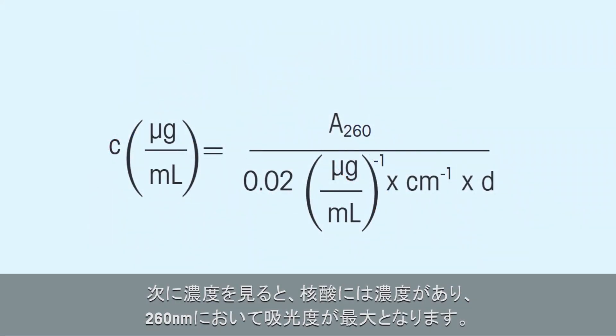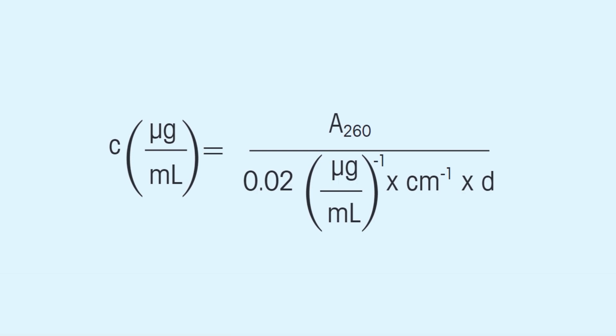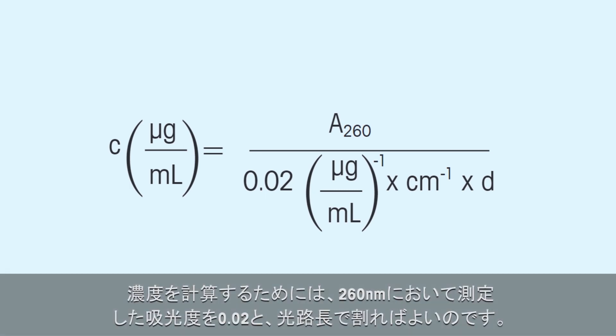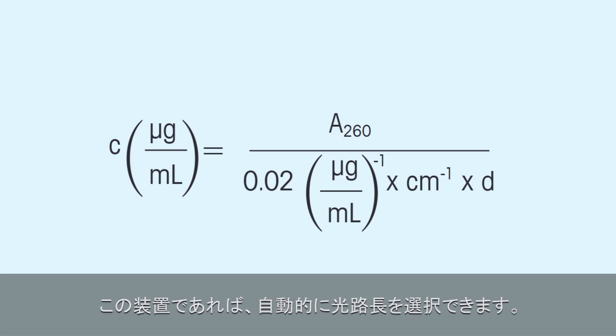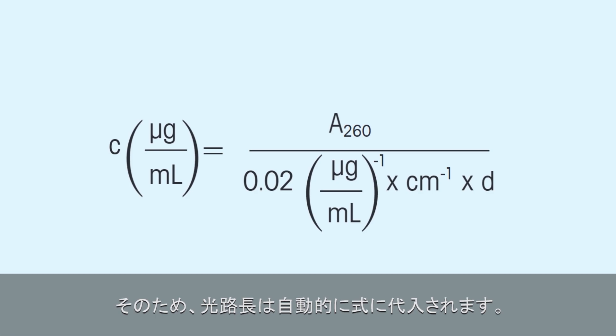When it comes to the concentration, the nucleic acid has an absorbance maximum at 260 nanometers. In order to calculate the concentration, we can divide the absorbance measured at 260 nanometers by 0.02, and by the path length. The instrument can select the path length itself, so the path length will be entered into the formula automatically.